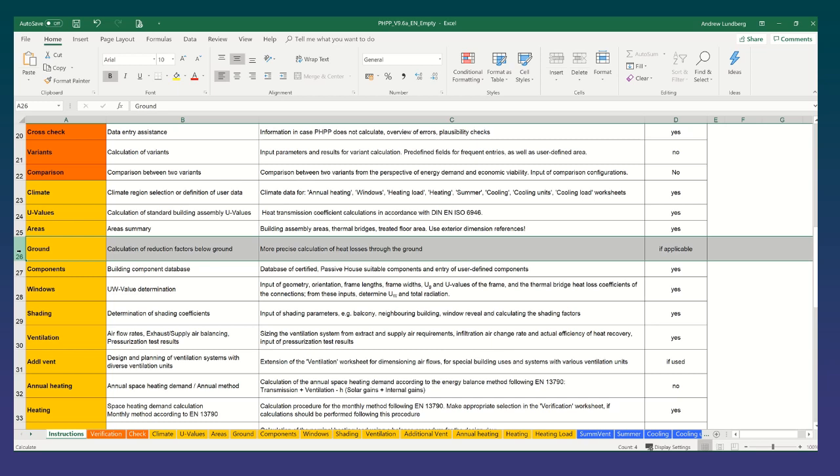So you do not have to enter in the ground sheet but it may be applicable for example especially if you do have flowing groundwater within maybe three meters of your floor slab for example that can significantly affect heat loss through the ground and because the ground does act as a fantastic battery for stabilization of temperatures and providing additional thermal resistance. So it may be required to input some parameters in the ground situation. Personally I always use the ground sheet and the reason is because you get accurate calculation of what's called the reduction factor for the ground which basically calculates the U value of your ground floor slab in accordance with ISO 13370 which you've looked at previously. It's not always the case that the reduction factor will get that bang on but it will be very close and will be reflective of the overall average annual performance of the ground room of the building.